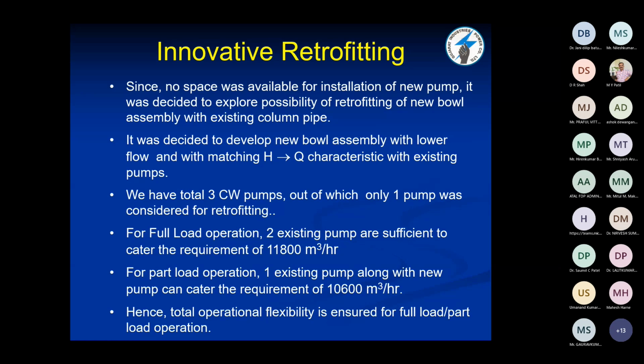Since no space was available for installation of a new pump, it was decided to explore the possibility of retrofitting a new bowl assembly with the existing column pipe. So the existing column pipe, the motor and everything will remain the same, but the pump will be new. The pump will be of low capacity. So it was decided to develop a new bowl assembly with lower flow, matching the characteristics of the existing pumps.